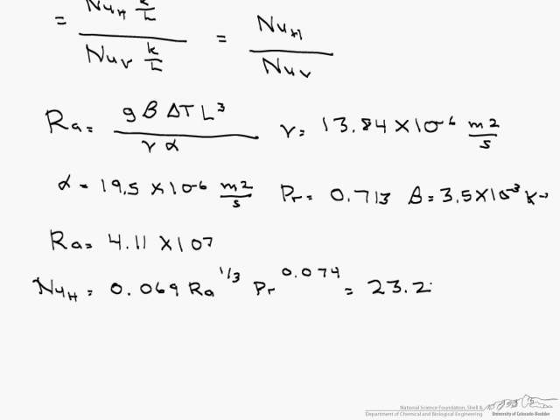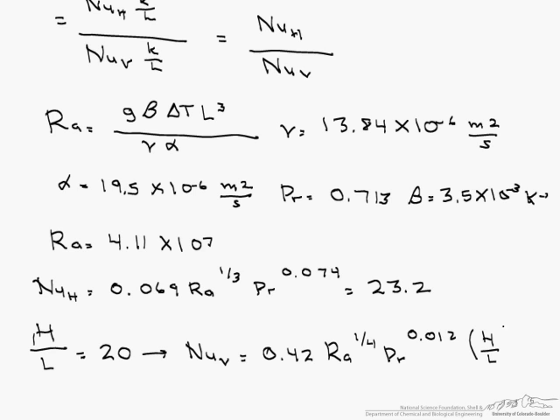In order to figure out the proper correlation for the vertical Nusselt number, we have to take a ratio of H divided by L, which is 20. Therefore, the proper correlation for our Nusselt number for the vertical enclosure is 0.42 times Ra to the 1/4 times Pr to the 0.012 times H over L to the minus 0.3.